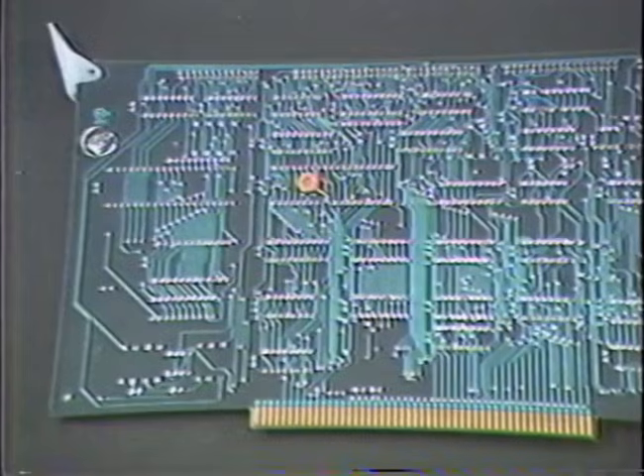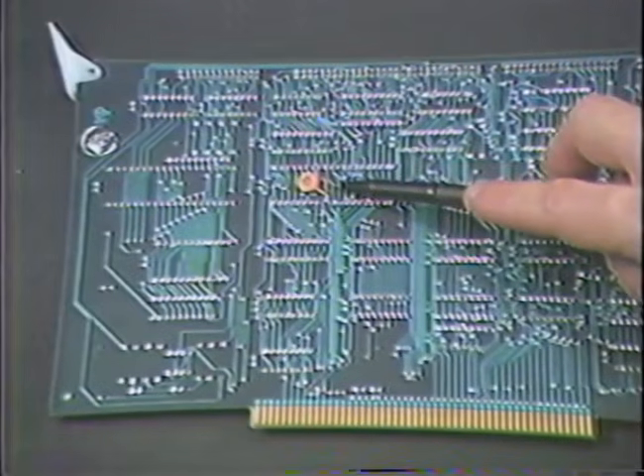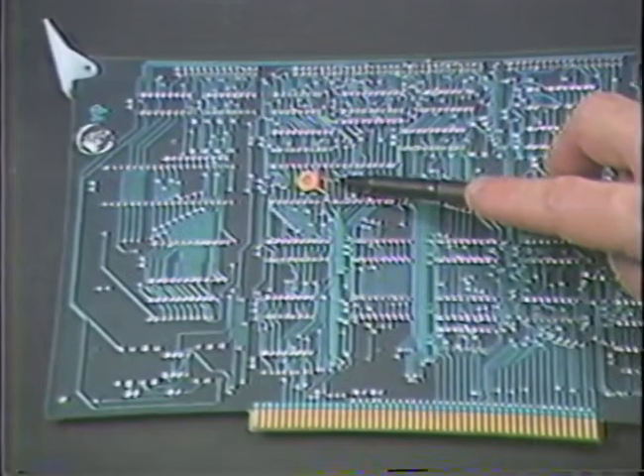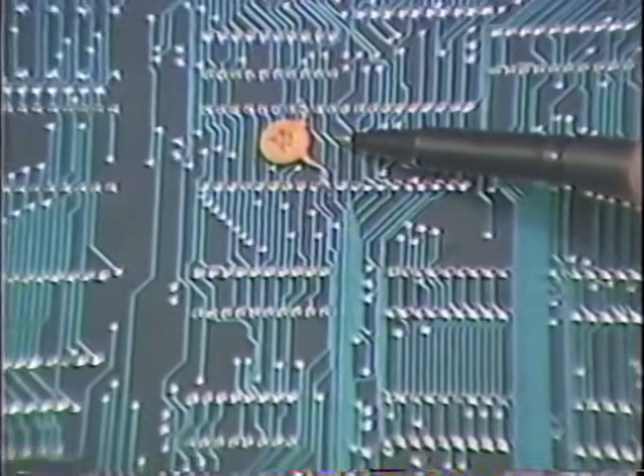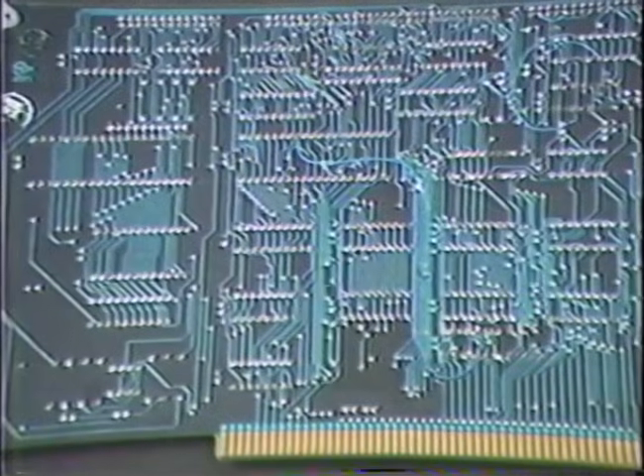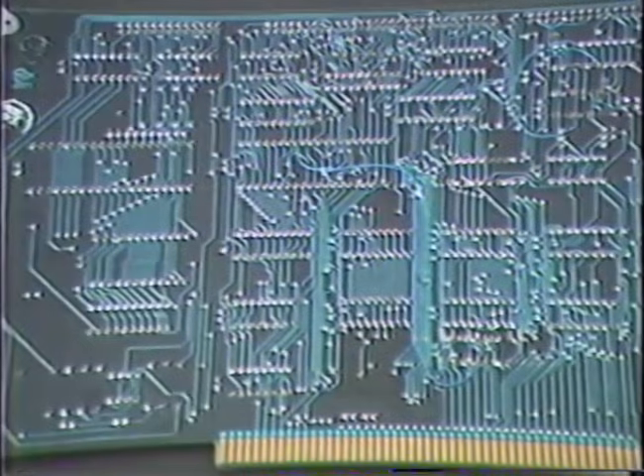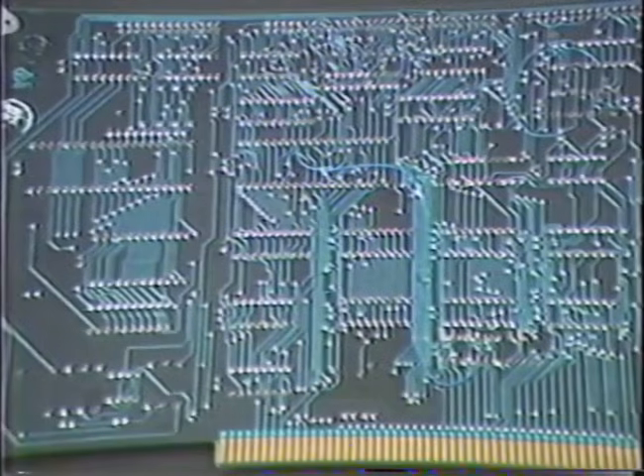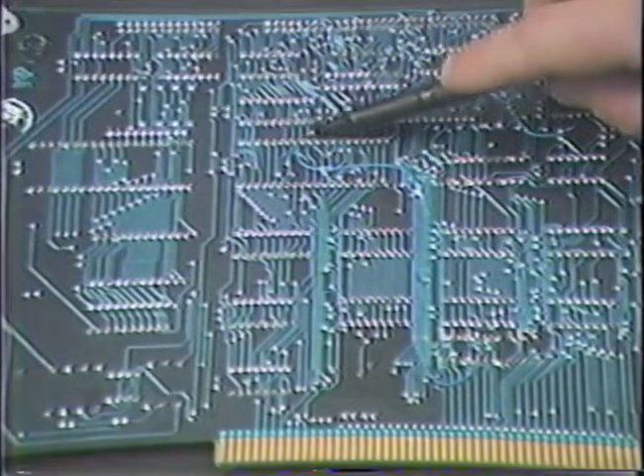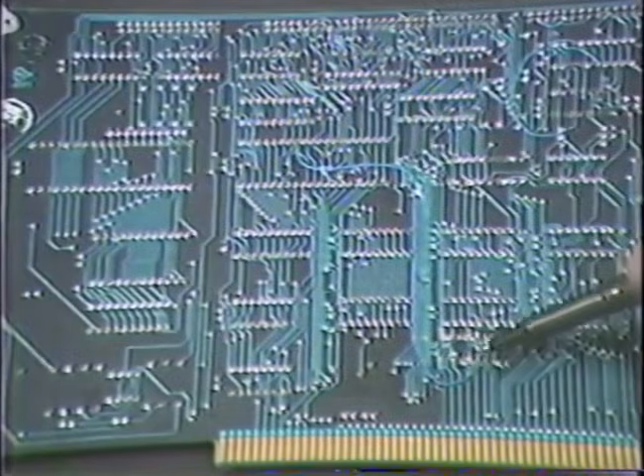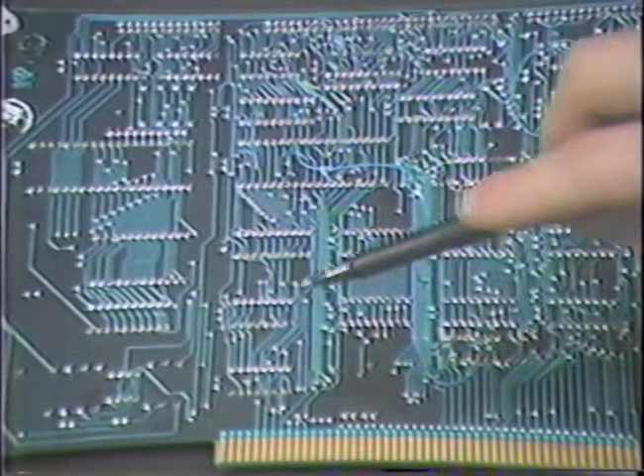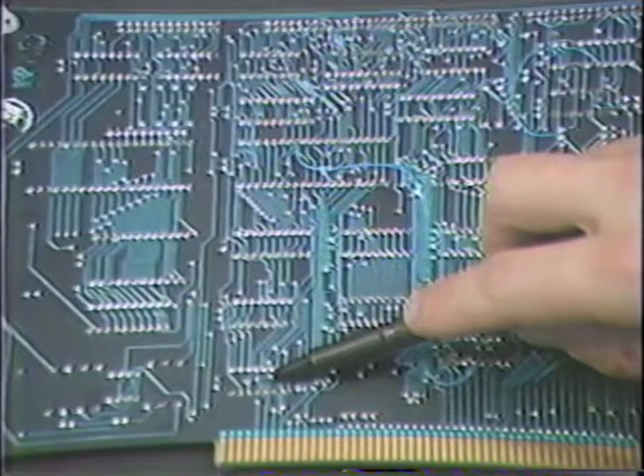This is due to an improper reset value on the clock timer located in IC30 on the CPU board. There are two fixes for this problem. The first we call the cap mod. A 2200 or 1800 picofarad capacitor is placed between pin 30 and pin 8 on the backside of IC30. The second way is used in current manufacturing and will work with version 1.21 software or greater. Instead of using the capacitor, the line is run through a buffer. Pin 8 of IC30 is jumpered to pin 13 of IC7. The trace at pin 14, IC1, is then cut at the pin.